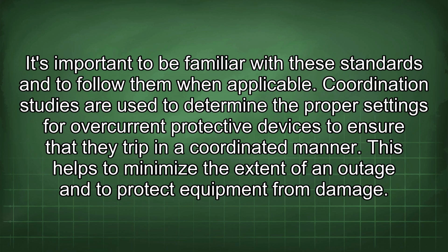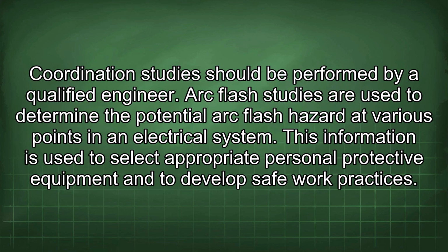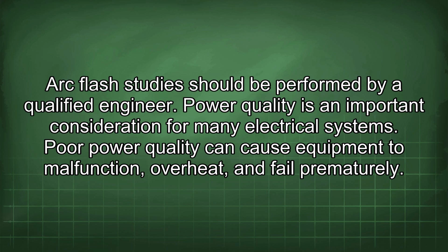Coordination studies are used to determine the proper settings for overcurrent protective devices to ensure that they trip in a coordinated manner. This helps to minimize the extent of an outage and to protect equipment from damage. Coordination studies should be performed by a qualified engineer. Arc flash studies are used to determine the potential arc flash hazard at various points in an electrical system. This information is used to select appropriate personal protective equipment and to develop safe work practices. Arc flash studies should be performed by a qualified engineer.